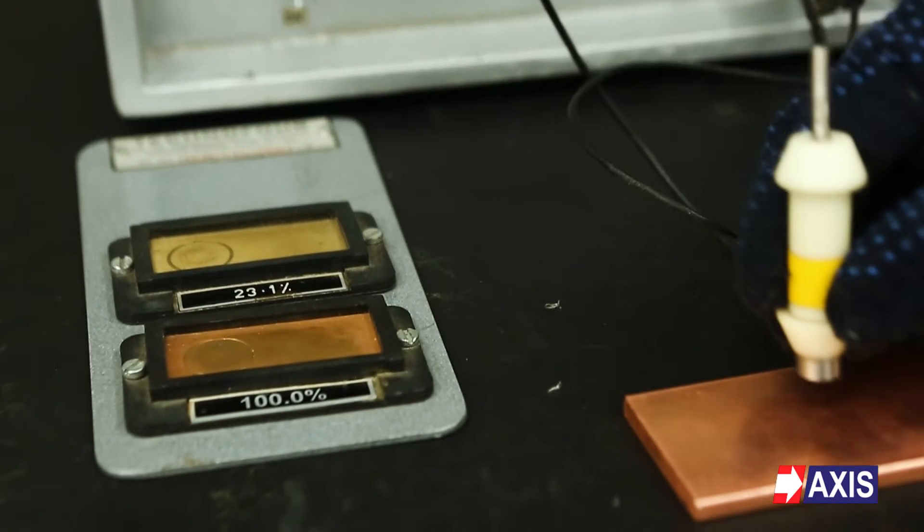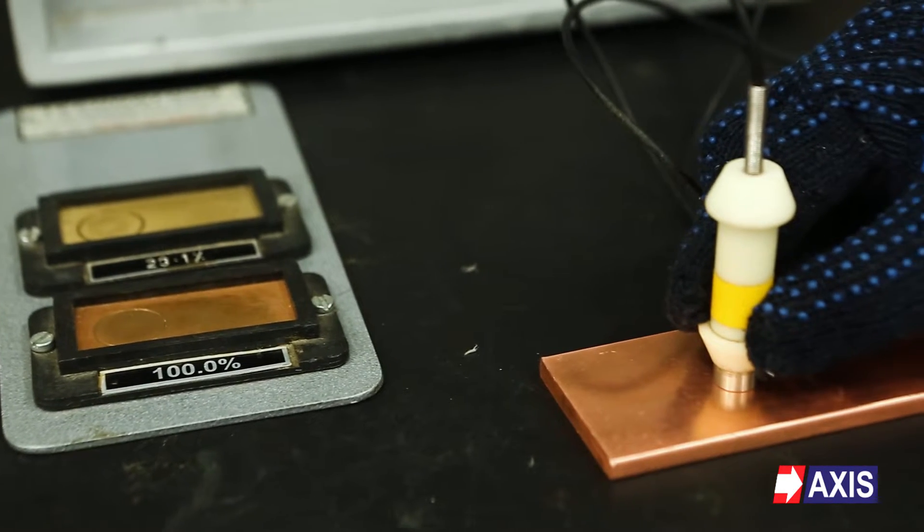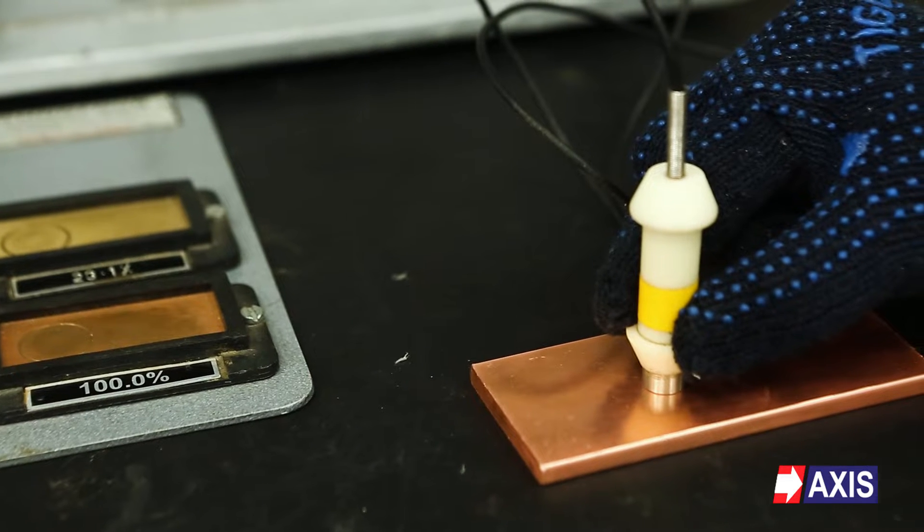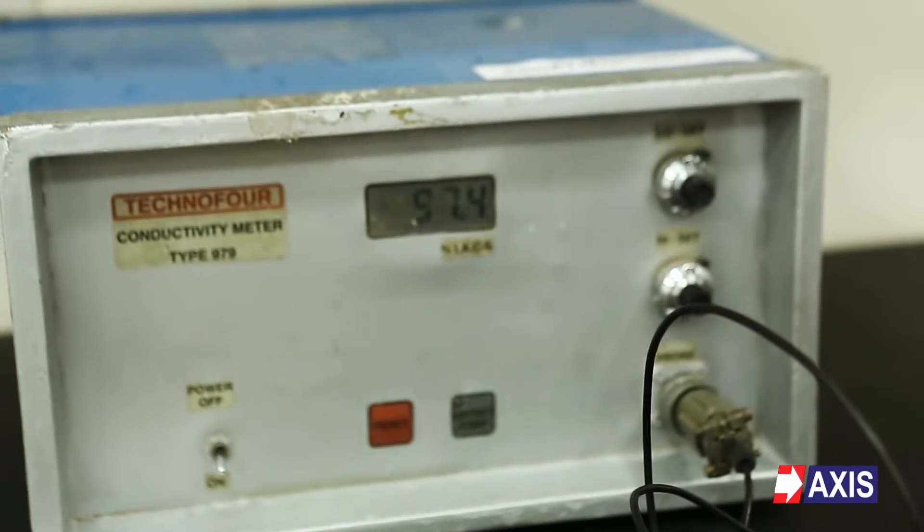The value displayed on the display unit is the electrical conductivity of the test piece. In the case of copper, the electrical conductivity must be more than 97% to ensure the material is electrolytic tough pitch or ETP grade copper.